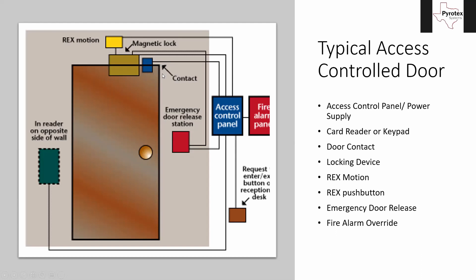Next is a door contact — a status indicator for the access control panel to know the door was opened and closed again. It can also double as a security intrusion sensor. Above the mag lock we have the REX motion sensor — REX means request to exit. This motion sensor is mounted on the ceiling inside the door, pointed down the hallway, so as someone approaches, it de-energizes the magnetic lock and allows the door to move.